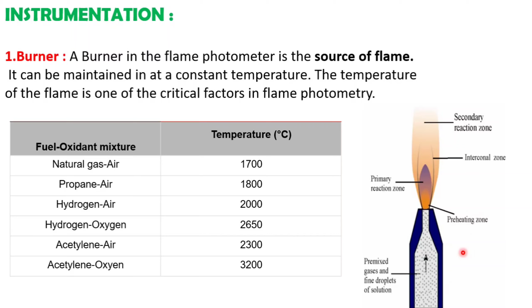The flame has some characteristics. The flame should be able to evaporate the liquid droplets from the sample solution, it should decompose the compounds of the solid residue into free atoms, and it should also be able to excite the free atoms. Different types of burners are used in flame photometry, and this is the total consumption burner, and another one, the premix burner, is also used.